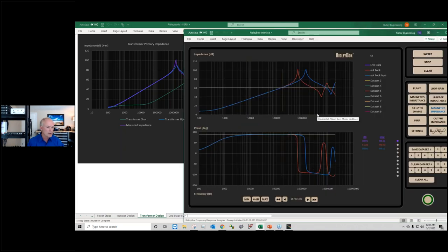Go back here again, busy sweeping the third transformer. No difference between them whatsoever. So if you're testing your transformer with an LCR meter, whatever method you use, if you're not sweeping the full frequency, you will not see a difference between these transformers. Most manufacturers do not do these sweeps, and most users and designers of transformers do not do these sweeps either. So they never get to a good design because they can't see the differences.